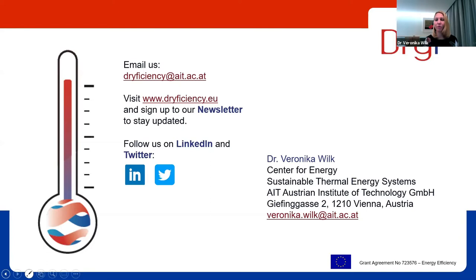It's not only the full scale for the drying application that we've seen here, but also related concepts looking into other heat sources. And that's also a very interesting feature that was not in the center of our project, because we really wanted to demonstrate the high temperatures. But from a process integration perspective, it's also important to take into account that the heat pump also provides cooling. So you can use the heat pump to take some pressure from the cooling equipment that's already there. And it's a good way to start for an integration point for the heat pump.